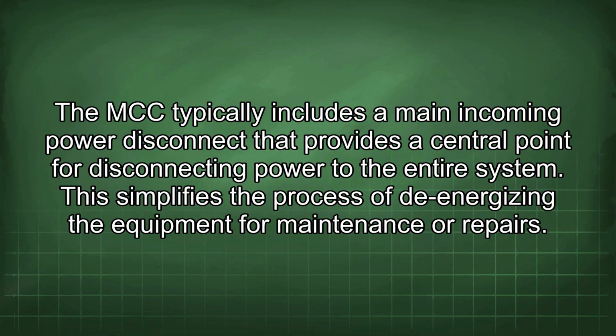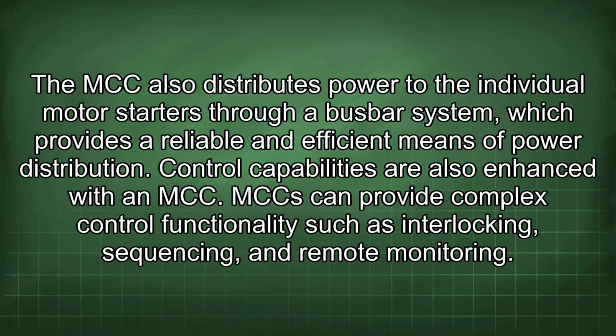The MCC typically includes a main incoming power disconnect that provides a central point for disconnecting power to the entire system. This simplifies the process of de-energizing the equipment for maintenance or repairs. The MCC also distributes power to the individual motor starters through a busbar system, which provides a reliable and efficient means of power distribution. Control capabilities are also enhanced with an MCC.